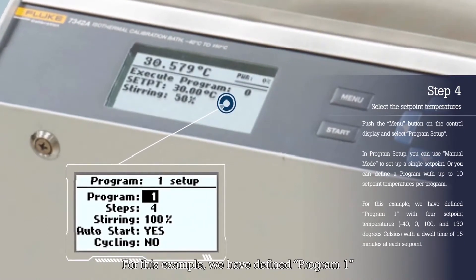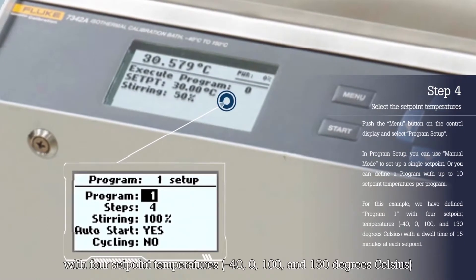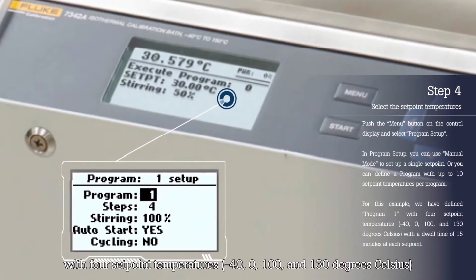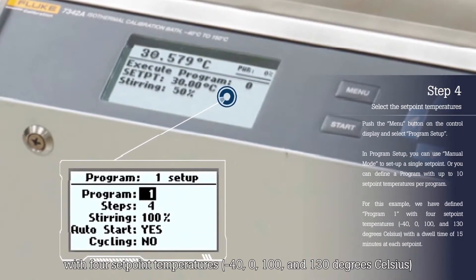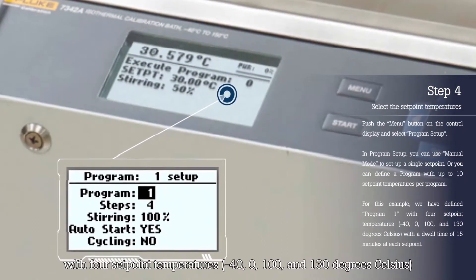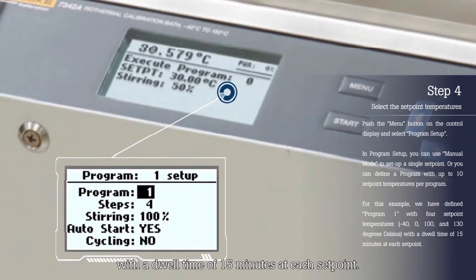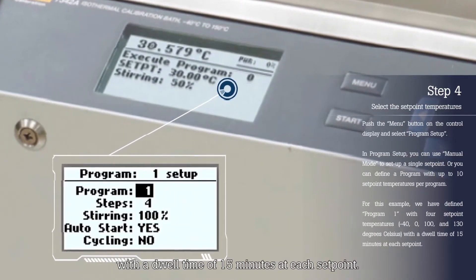For this example, we have defined Program 1 with four set point temperatures: minus 40, 0, 100, and 130 degrees Celsius with a dwell time of 15 minutes at each set point.